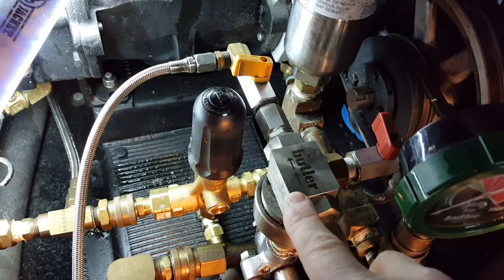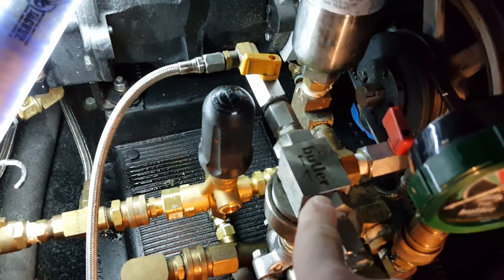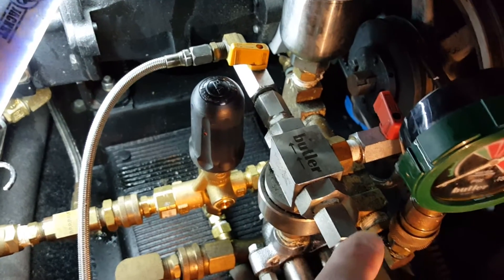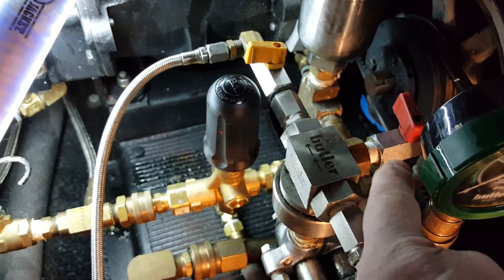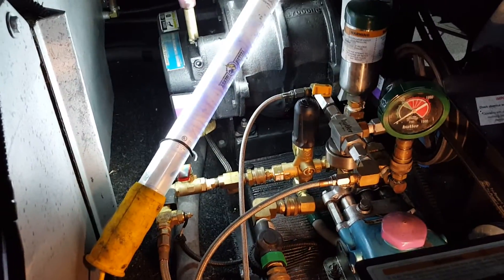Look at what your plunger looks like — there's a plastic disc in there. Just put them back together the way it came apart. Note these arrows showing the direction of chemical flow. Snug it up, make sure you use Teflon on the joints where appropriate, and you're good to go. Bleed it — I have another video on how to bleed the system. Set your meter and you're back in business. Give me a shout if you have more questions.